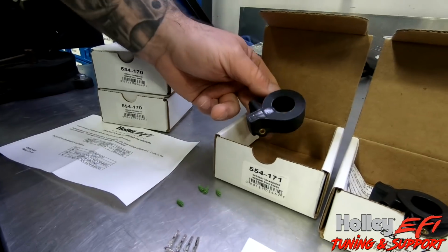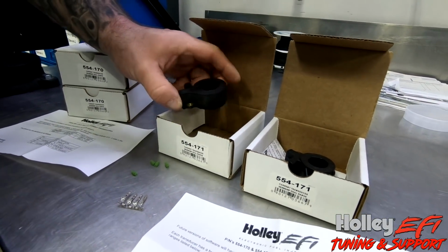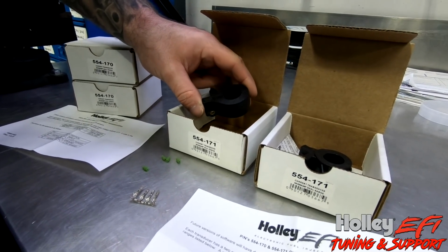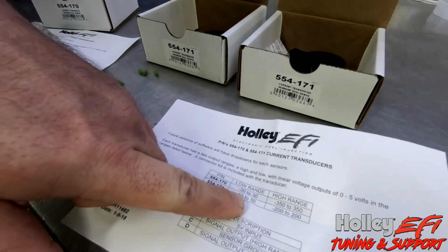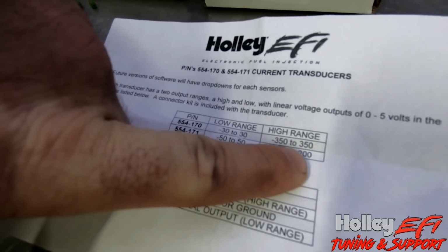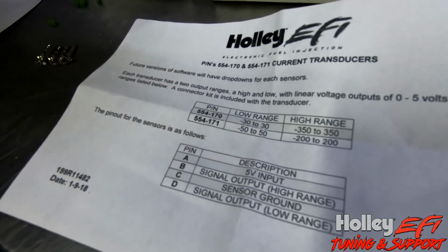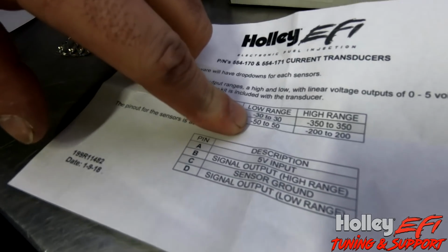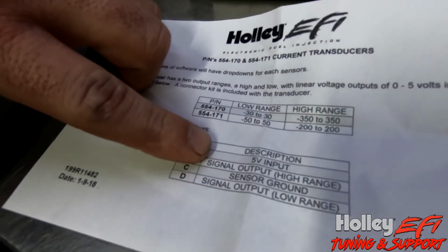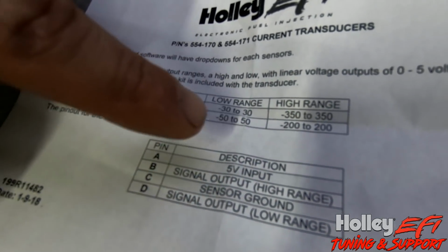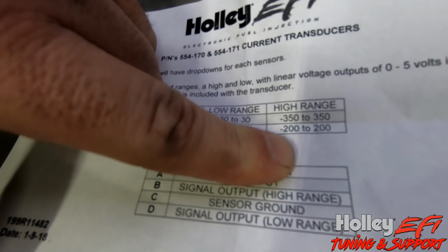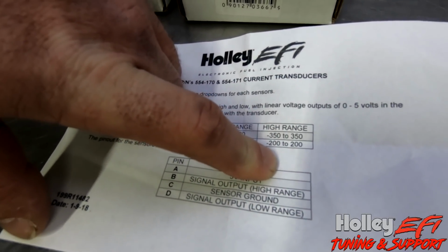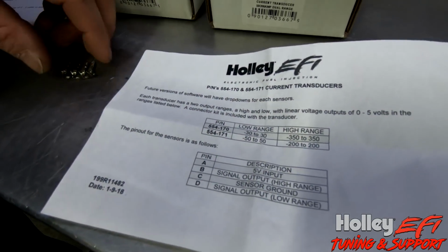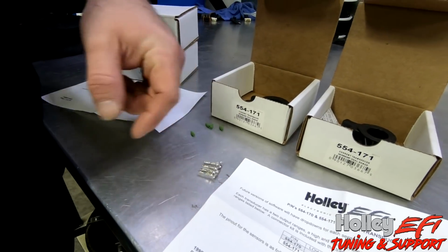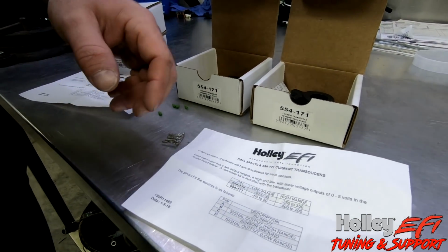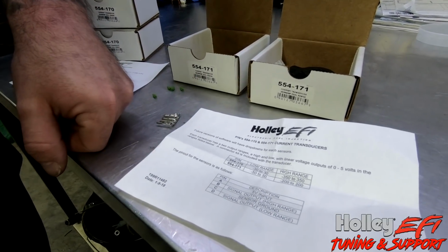Pick whichever range you want based on what you think your amperage draw is going to be. You can set these up minus 30 to plus 30, or minus 350 to plus 350 amps. You wouldn't want to use the low range output on an alternator since it should put out more than 30 or 50 amps, and your coils aren't going to need 200 amps, so don't use that range for coils. Just pick whichever range fits. I haven't tested it, but I'm assuming you could probably shove 2 different wires through it and monitor both, though you'd need pretty distinct differences in amperage draw across the two.